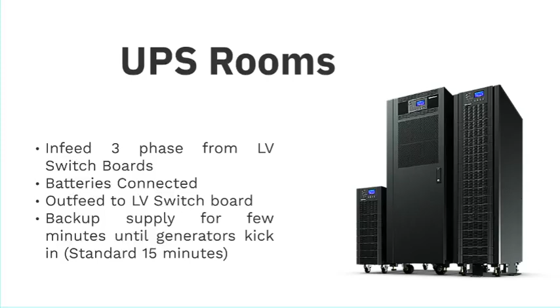There can be another room which is a UPS room where UPS units are stored, and since UPS need batteries, there can be separate battery rooms. In some small data centers, a low voltage switch room can have UPS and battery rooms as well. These three things can be in the same big room or in three different rooms.